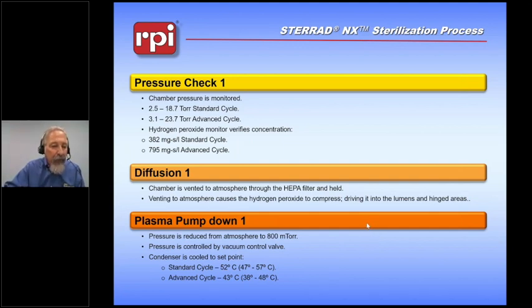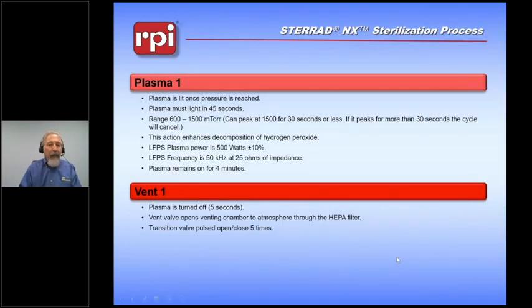Once we've got the plasma pumped down, we then turn on the plasma, which spreads through the entire material in the chamber, and that plasma must light within 45 seconds. The machine can tell when the plasma is lit, and during the actual process of generating the plasma, we will also pull a much more solid vacuum, making sure that we have all of that peroxide where it can go. We want to be sure it's completely diffused.